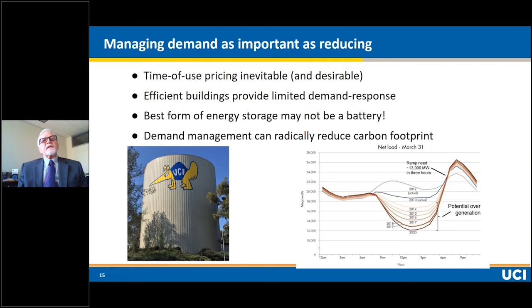So that's why this makes a lot of sense. Here's a picture of it with the anteater painted on it. This is just saying the best form of energy storage may not be a battery. In that duck curve you see over on the right, we can shift our load anytime we want in a 24-hour day, because when that tank's fully charged to 38 degrees, you can run the whole campus on the hottest day of the year without running a chiller at all. It allows you to move that load around to do load management at the enterprise level, not the building level.